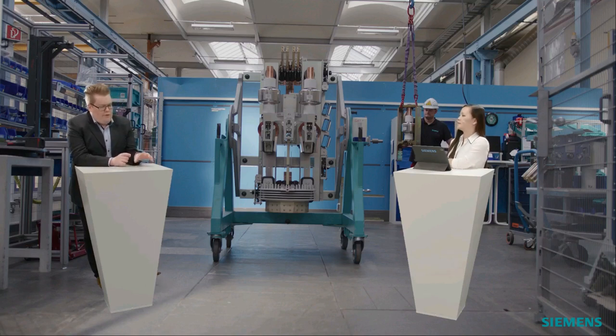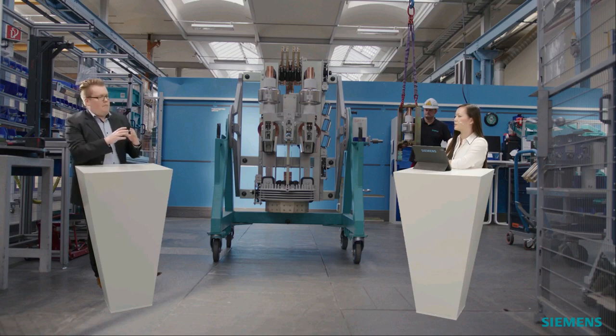Sure. What I said is that the out-of-phase is only important for the fault synchronization. So the IEC IEEE standard only requires a type test with an out-of-phase angle of 90 degrees. But there might be some cases where the out-of-phase angle can be up to 180 degrees.